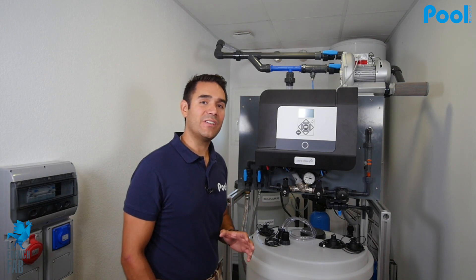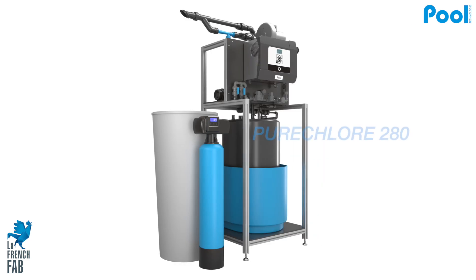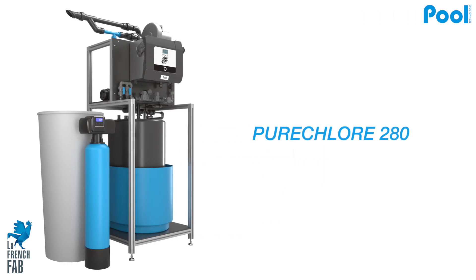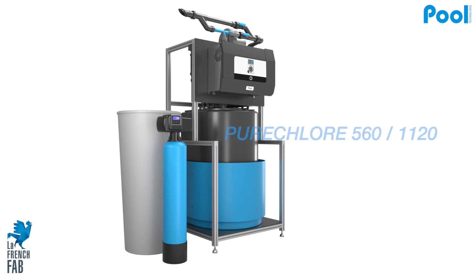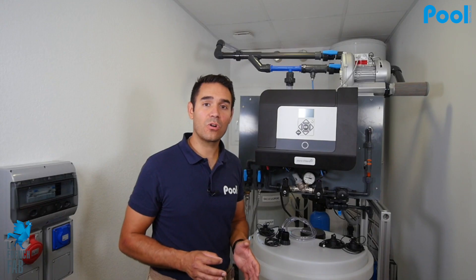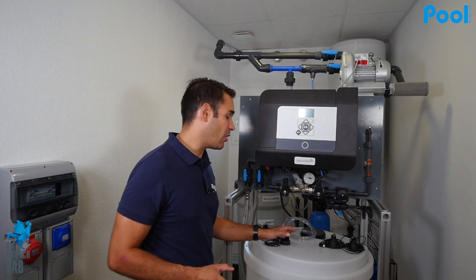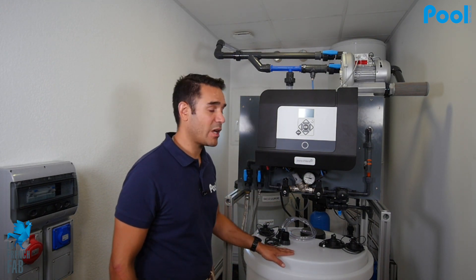The PureChlore produces sodium hypochlorite with a concentration of 8 grams per liter. We have different models starting with the PureChlore 70, which makes the equivalent of 70 grams of pure chlorine per hour, up to the PureChlore 1 Kilo, which makes the equivalent of one kilogram of pure chlorine per hour.